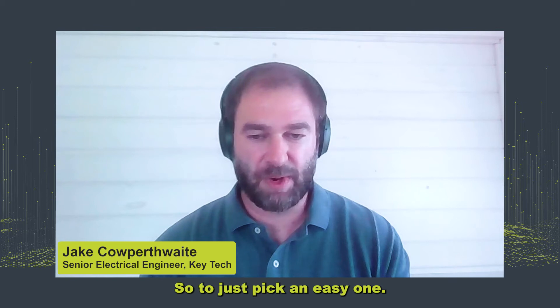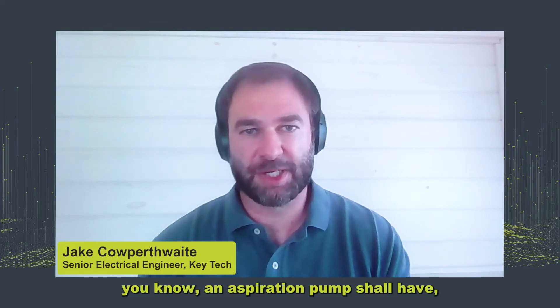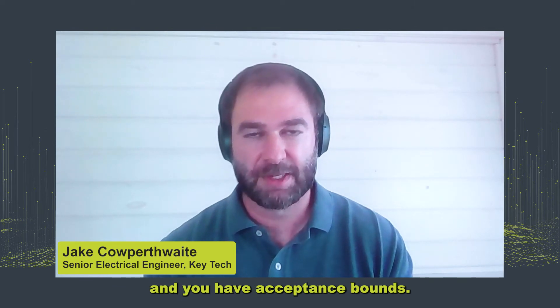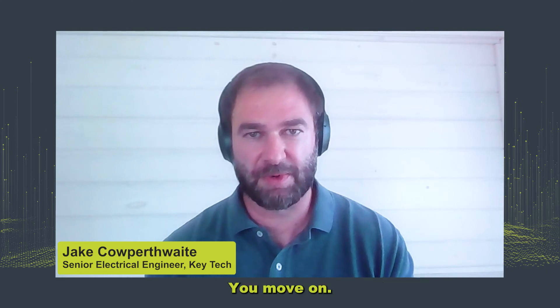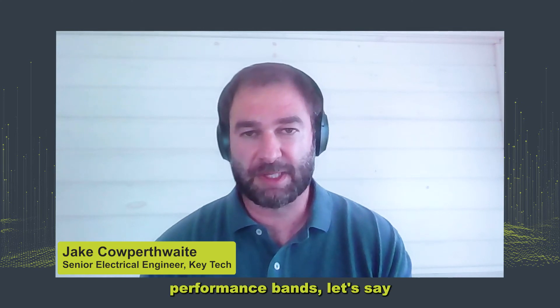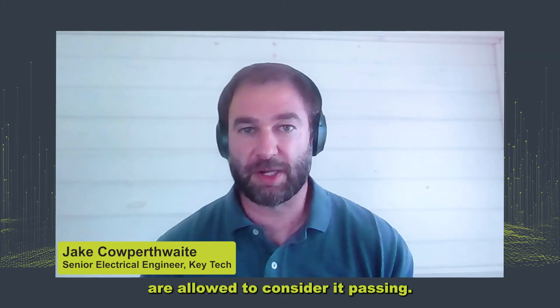At KeyTech, we deal with pumps a lot, so a requirement might be: an aspiration pump shall have X flow rate within plus or minus Y percent. It's very clear — you have a flow rate and you have acceptance bounds. You run a test, you prove it's within that range, and you move on. But if you don't have performance bounds — say the flow rate shall be X — you may run the test and it may not be exactly as stated, so you need to define what limits are allowed to consider it passing.